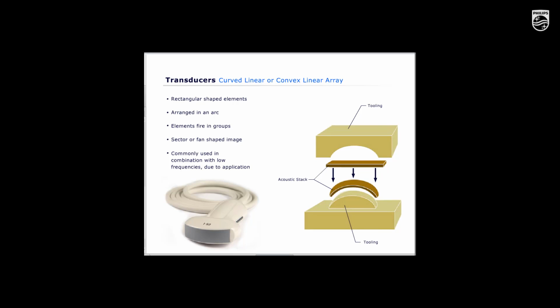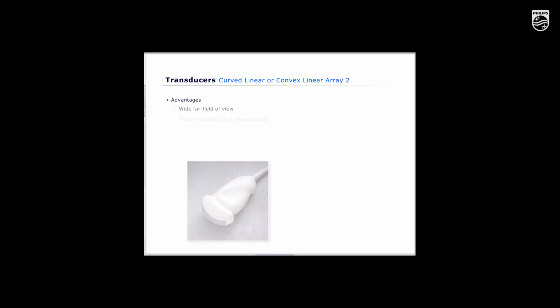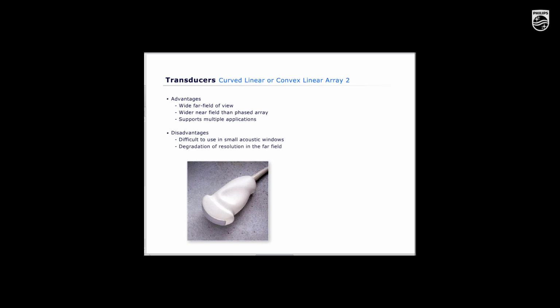Usually a curved array transducer is combined with lower transmit frequencies, as the application that is used requires deep penetration. As a side note, during manufacturing, the linear array stack is bent into the curved shape of the transducer, as you can see in the illustration. Some properties of the curved linear transducer are a wide field of view, and it is difficult to use in small acoustic windows, such as the chest cavity.